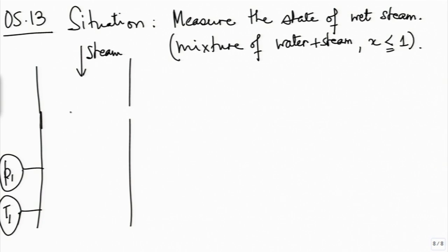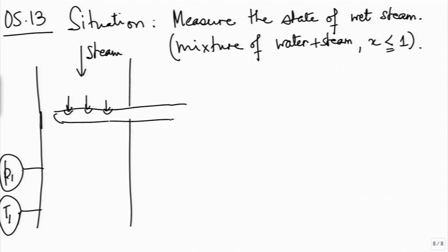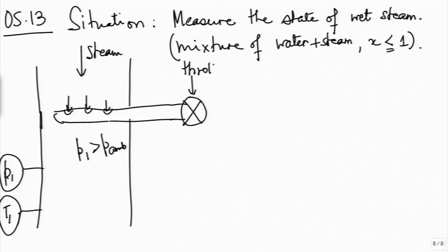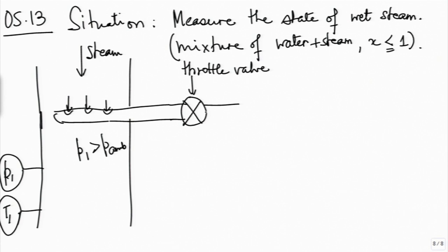What we do is take a sample out—maybe we put a tube with some holes so a representative sample is taken out. It is expected that P1 is greater than P ambient, so if this is connected on the other side to the environment, steam will start flowing through it and a large amount of steam will flow. Since we want only a sample, we put what is known as a throttle valve—a valve which is only partially open, or sometimes a small orifice or a series of orifices. The job of this throttle valve is to provide enough flow resistance so that even with the large pressure difference between P1 and ambient, only a small amount of steam flows through this.